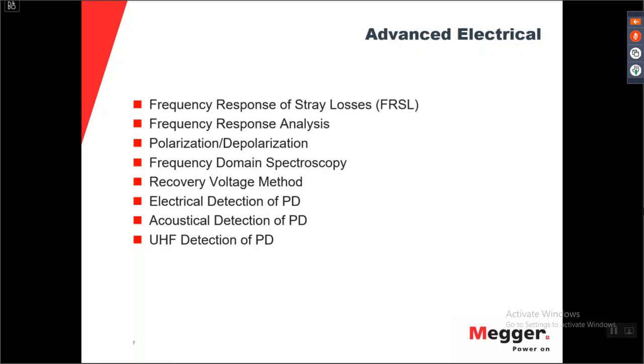So we will go through the frequency response of stray losses and the frequency response analysis, which is the FRA or the SFRA test. Then you have 3 tests, which are polarization and depolarization currents, frequency domain spectroscopy, and recovery voltage method. This is PDC, FDS, and RVM, as it's usually said. Those 3 tests are actually very similar. If we say, for instance, the turns ratio, the TTR test, it is very unique for finding the turns ratio of the transformer, while with the polarization current and the frequency domain spectroscopy, you're actually looking to find the same thing, but it's just 2 different ways of doing it.